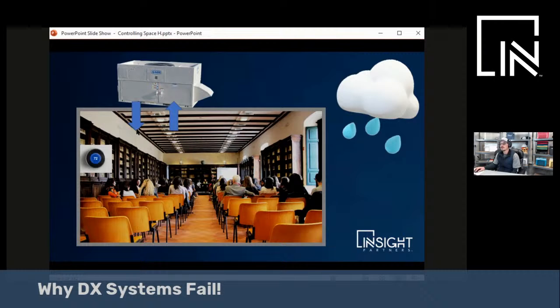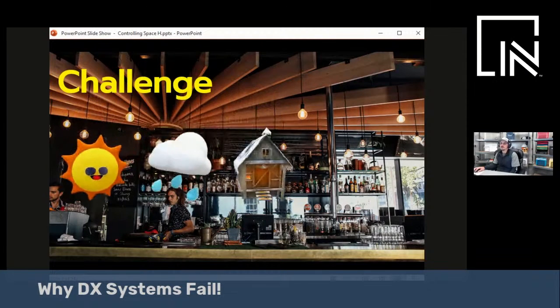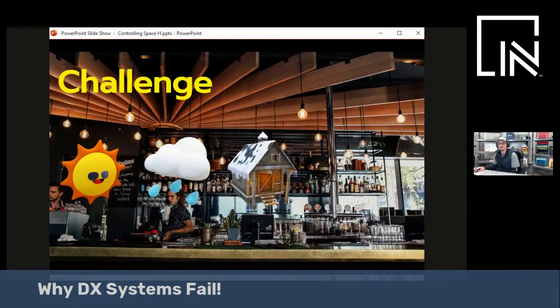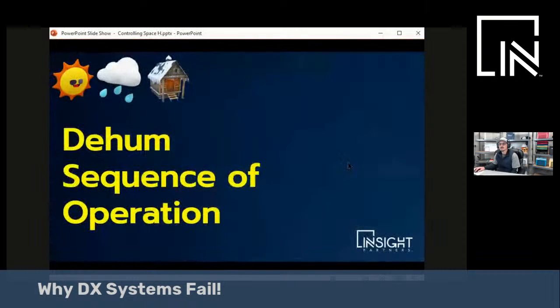The system will shut down, even if you need to dehumidify, because it's only looking at the space temperature. It's not looking at the humidity in the space for standard DX systems. And there's the problem. So the challenge is to design a system that will control temperature and humidity over all load conditions. Normal systems aren't designed to do that.